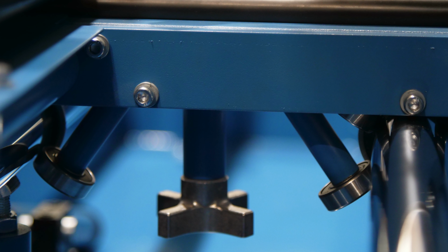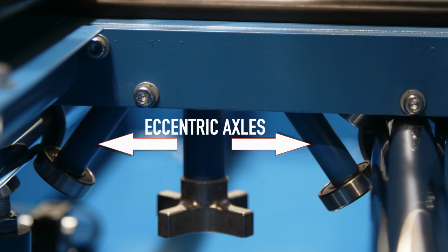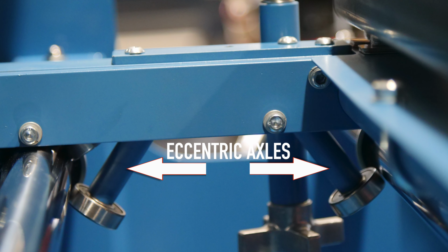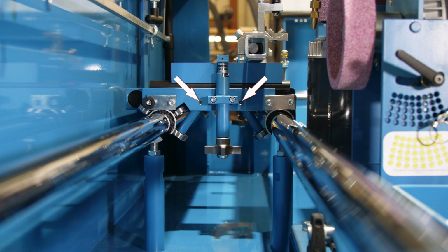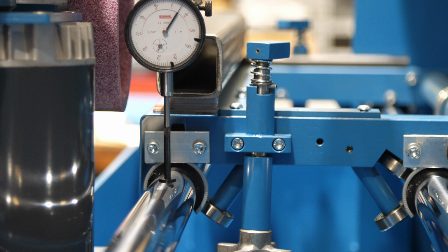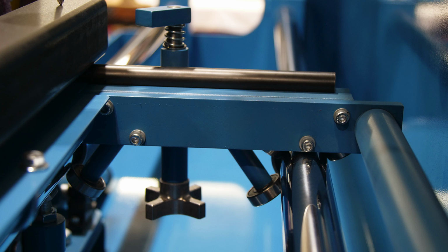Step 1, make sure these 2 bearings on the bottom of the carriage on the leading side are not touching the chrome bar. Also, make sure the 2 bearings on the bottom of the trailing side of the carriage are not touching the chrome bar either. You can loosen the set screws here in order to rotate the bearing axle away from the chrome bar. And just a friendly heads up that the set screw for the trailing side front bottom bearing is behind this pallet clamp. You'll then check the carriage for any rock on top of the chrome bars.